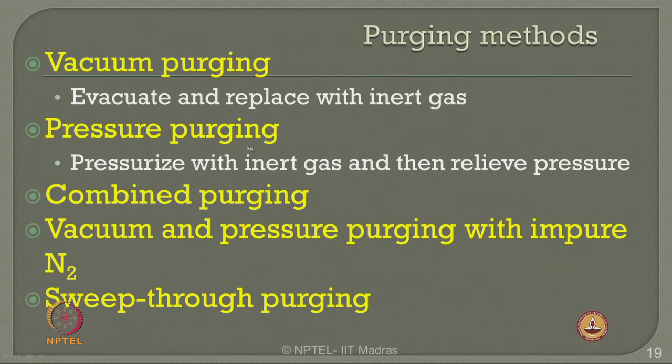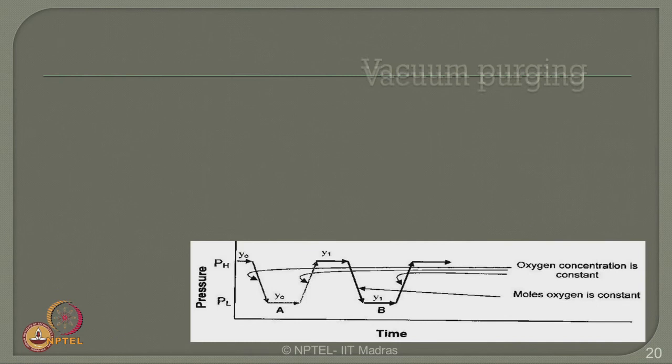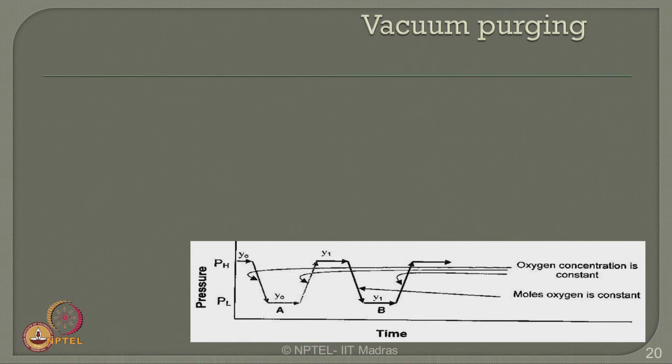In vacuum purging, we evacuate and replace with inert gas completely. In pressure purging, we pressurize with inert gas and then relieve the pressure from the system. One can also do siphon purging. Let us look at vacuum purging: it is one of the most commonly used methods for inerting contained vessels. The procedure is: draw vacuum on the vessel, relieve the vacuum with inert gas, and repeat the cycle until the desired concentration is reached.